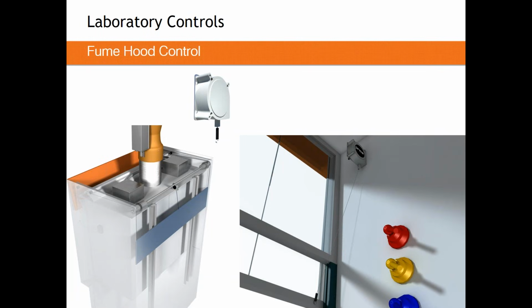We know if we want to maintain, let's say, 100 feet per minute, that it's really easy to calculate how much airflow will be required to achieve 100 feet per minute. So for example, if you have 10 square feet of open area, it will take 1,000 CFM approximately to achieve 100 feet per minute there. That's all sash sensing is. It's an open loop control strategy for fume hoods.